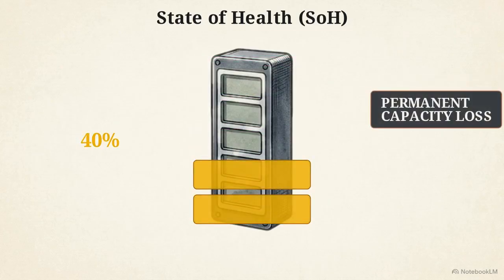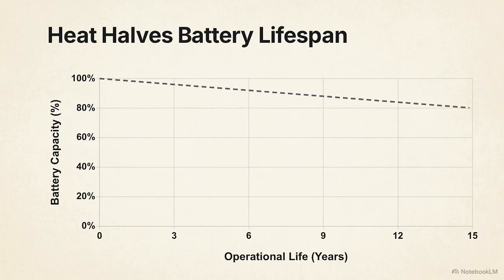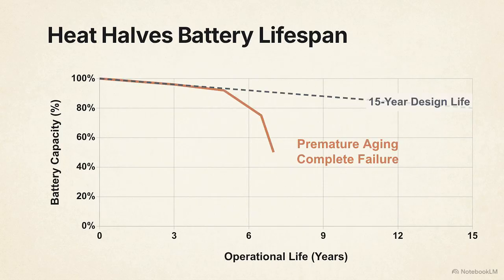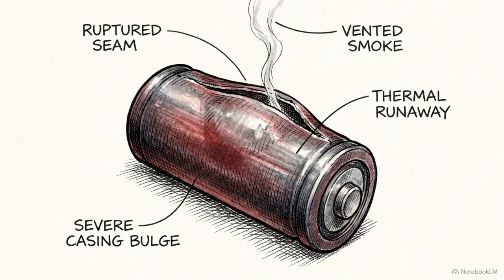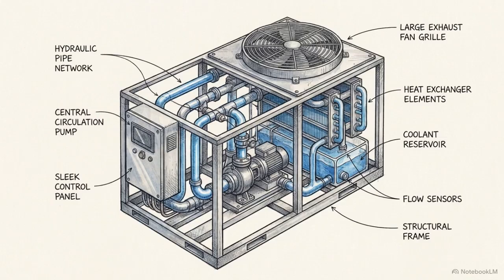First, the cells experience immediate capacity degradation. Then, the internal chemistry ages prematurely, cutting the lifespan of the battery in half. If the temperature continues to rise unchecked, the cells enter thermal runaway. The engineering solution to this thermal penalty is an active, deterministic dual-loop cooling architecture, commonly known as a BESS chiller.